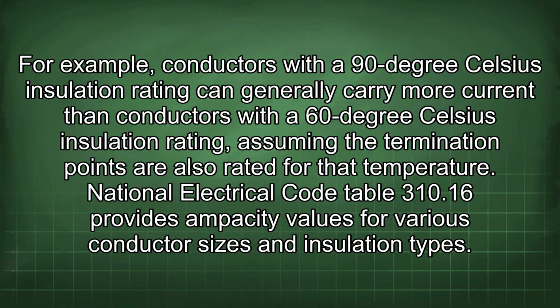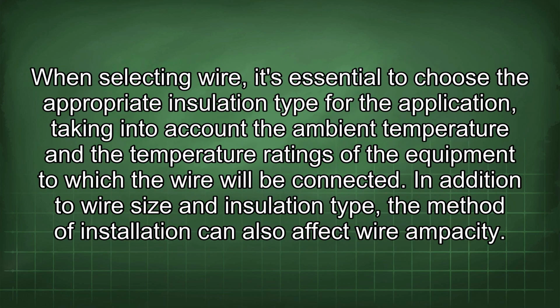National Electrical Code Table 310.16 provides ampacity values for various conductor sizes and insulation types. When selecting wire, it's essential to choose the appropriate insulation type for the application, taking into account the ambient temperature and the temperature ratings of the equipment to which the wire will be connected. In addition to wire size and insulation type, the method of installation can also affect wire ampacity.